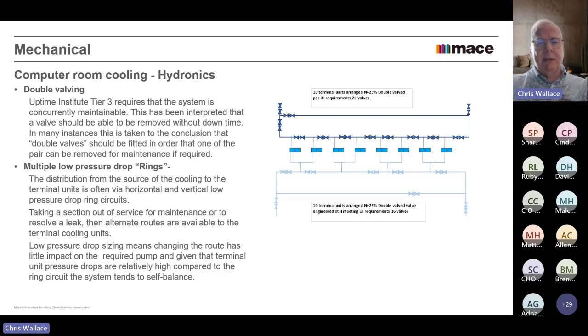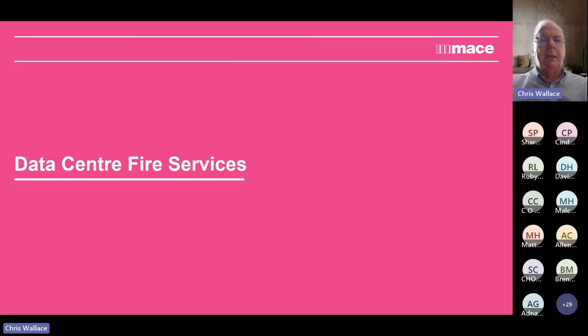Another benefit of this is that the low pressure drop means that, whichever way you're running, because the majority of the resistance is always in the terminal unit, it's going to tend to self-balance, and you're unlikely to have problems with pump performance, because all the resistance is going to be in the terminal compared to the low pressure ring mains.